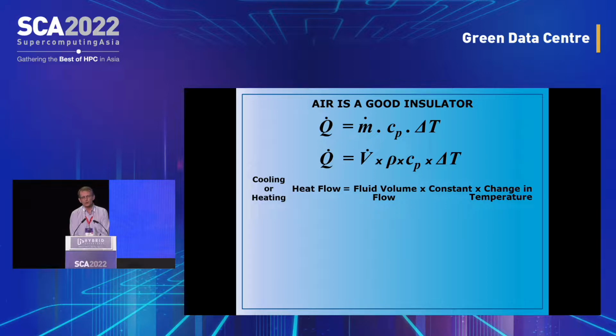If we're working to a particular temperature and we want more heat flow, more cooling, more movement of the heat, we need more volume flow. So let's look at air as that fluid. Air has a density of 1.185 kilograms per cubic meter and a specific heat of 1.006, which translates to a relatively constant factor of 1.19. That's basic physics, you cannot change the laws of physics. That's as good as we can get from air.